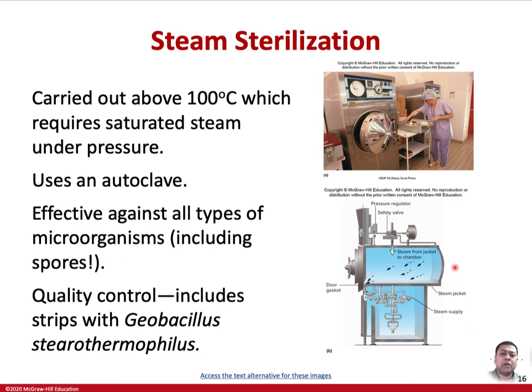There is also another thing that goes with that: how do we know that the material has been properly sterilized? There are some specific things that are used. There are some autoclave tapes, and they have some white marks on them, and you can put them onto the material that you are sterilizing. After they come out, you will see those white stripes have turned into black stripes. Those are heat sensitive stripes. What we mean by that is if the temperature of the chamber reaches 121 degrees Celsius, then those white stripes will turn into black stripes.